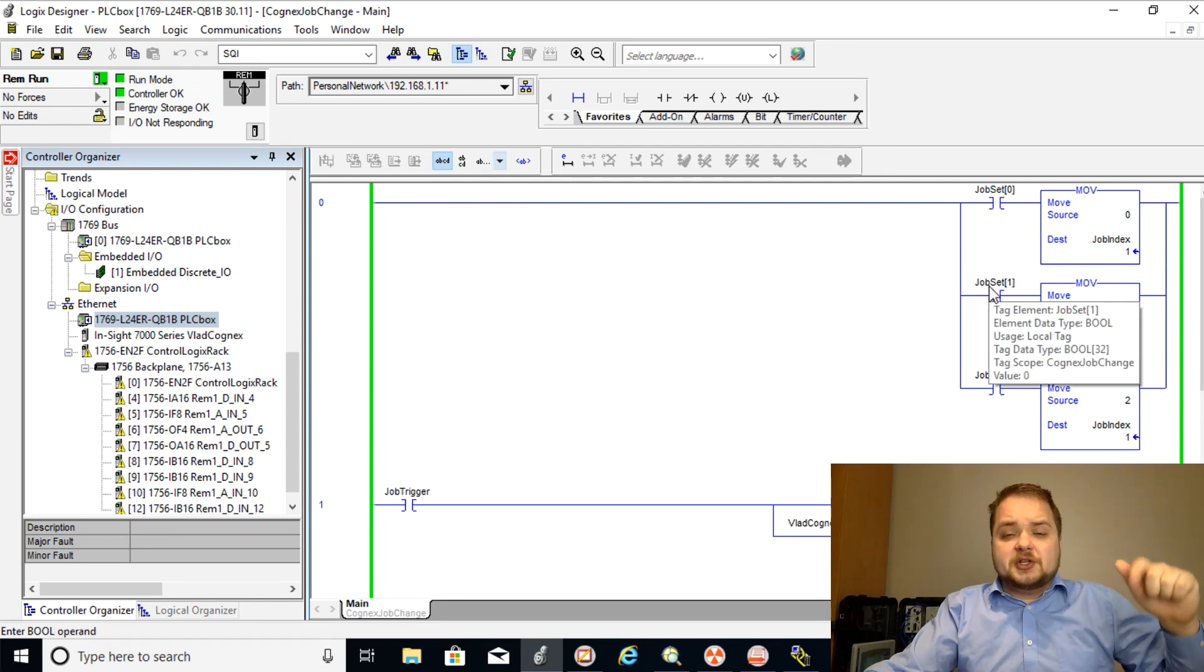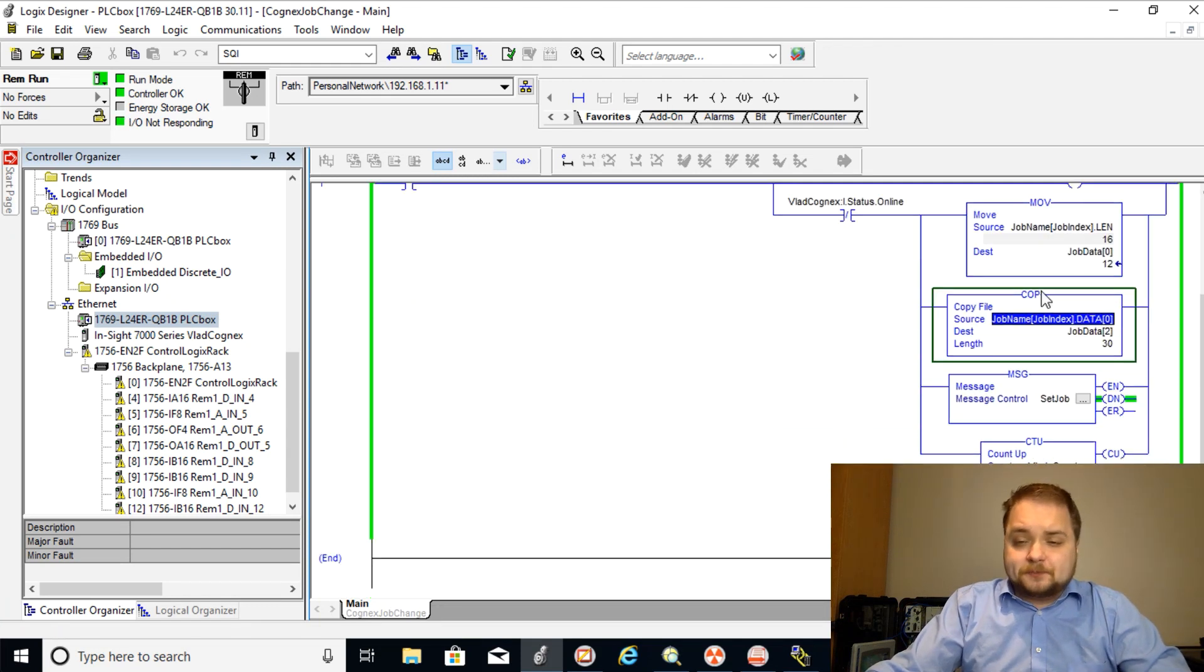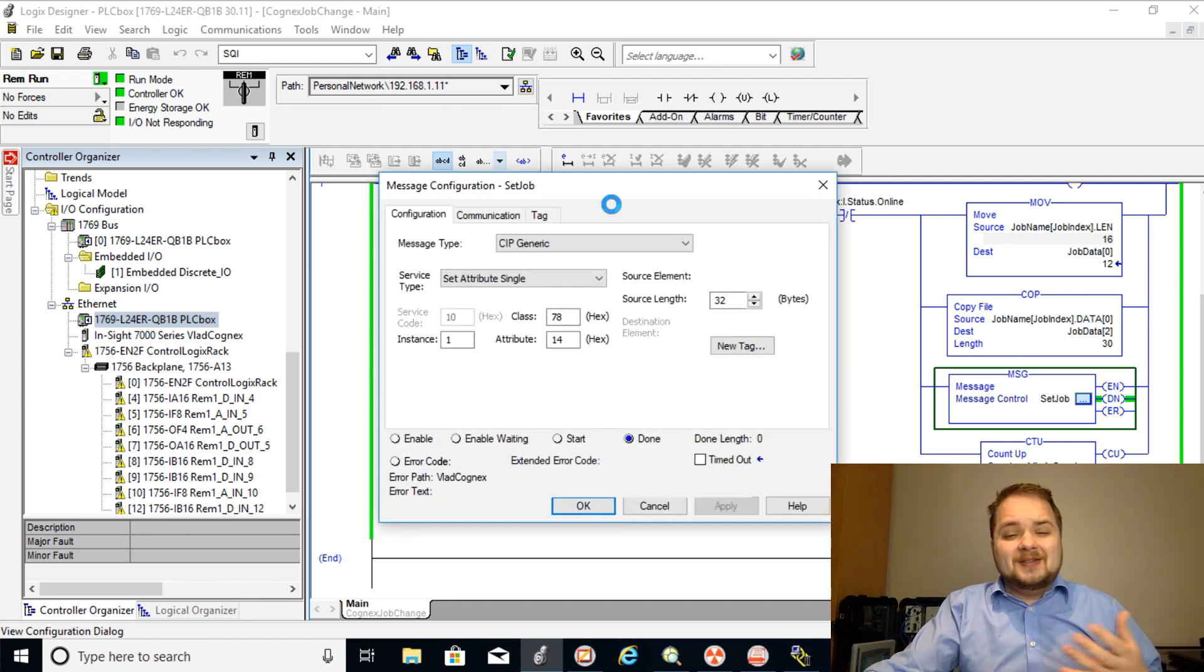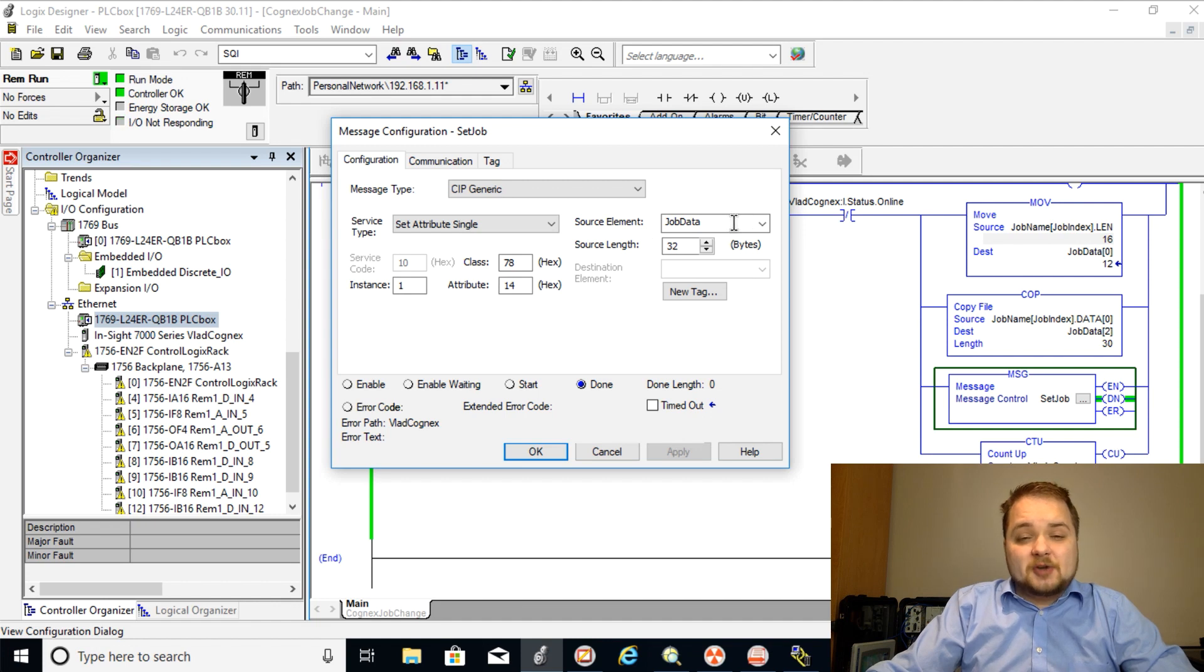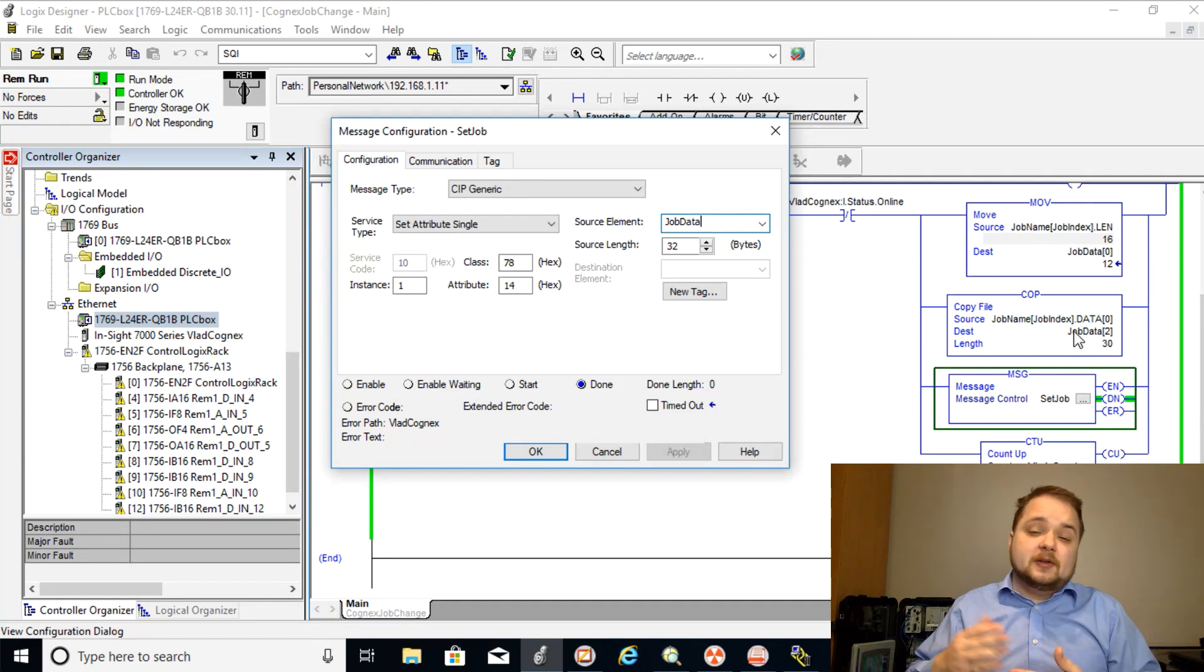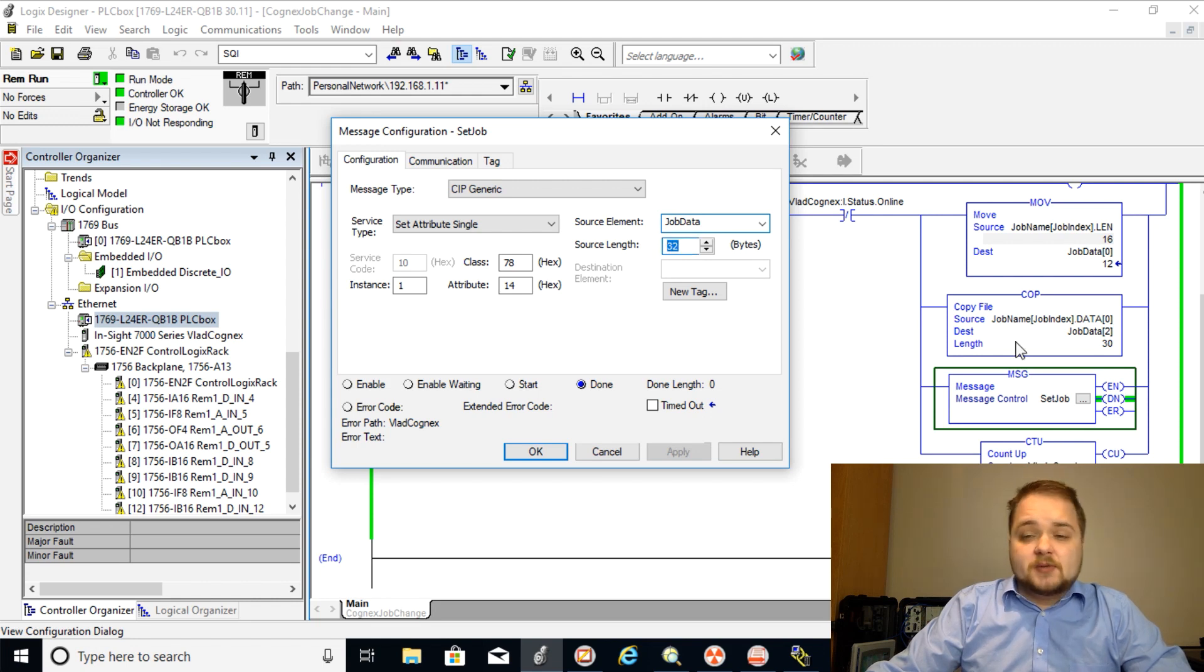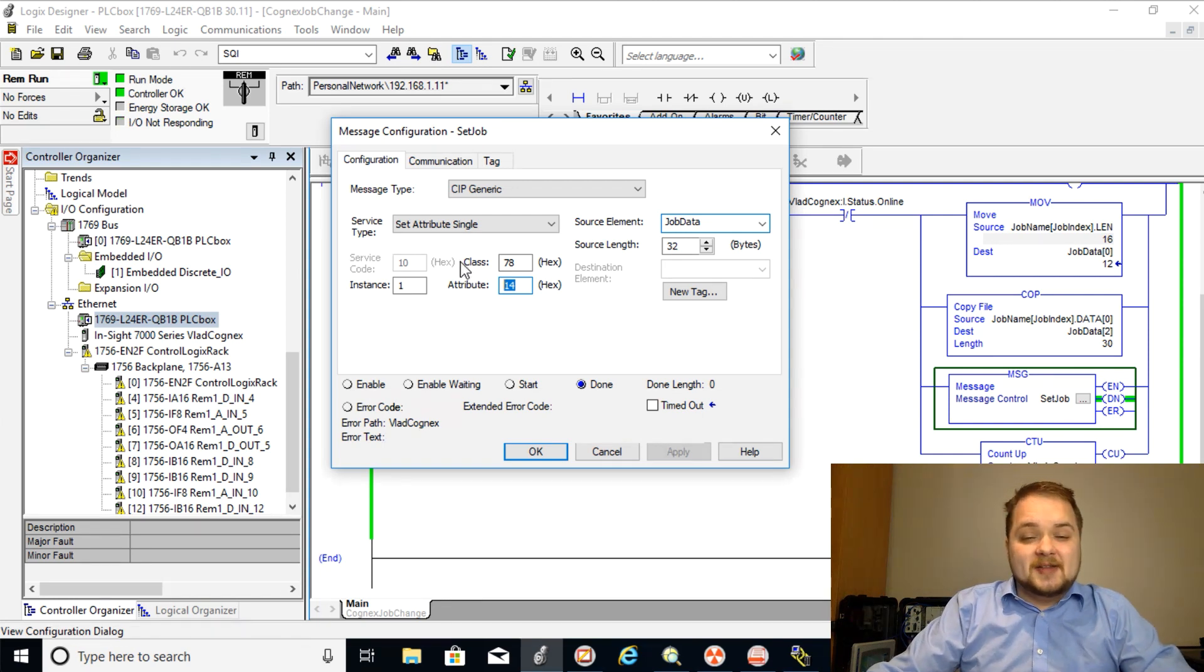Anyways the next important instruction that we need to look at is the message instruction. So the message instruction I've actually copied a lot of the parameters from the documentation of Cognex and they described that it needs to be a CIP generic, it needs to be set attribute single, it's also going to take the job data. So remember this is the packet that we've created, two first bytes of which are going to be the length of the job name and then the other 30 bytes are going to be the job name. So therefore the full length is going to be 32 bytes which is also specified in the job data length. In terms of class 78 and instance one attribute 14, this is straight from the documentation of Cognex, they give you all those values the way they should be set up.